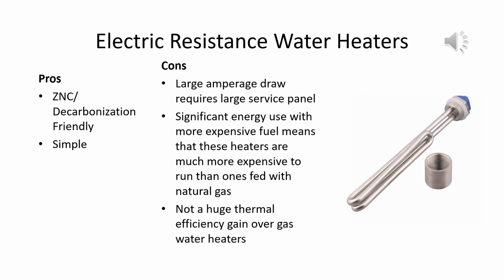Electric resistance water heaters are not very common in the commercial food service industry. The pros of these units are that they are zero net carbon and decarbonization friendly because they only use electricity. They are also simple and easy to work on. The cons are that they have a large amperage draw, which would require a relatively large service panel for commercial kitchen-sized loads. This would also lead to significant energy use with a more expensive fuel. That means that these heaters are much more expensive to run than ones fed with natural gas of similar size.